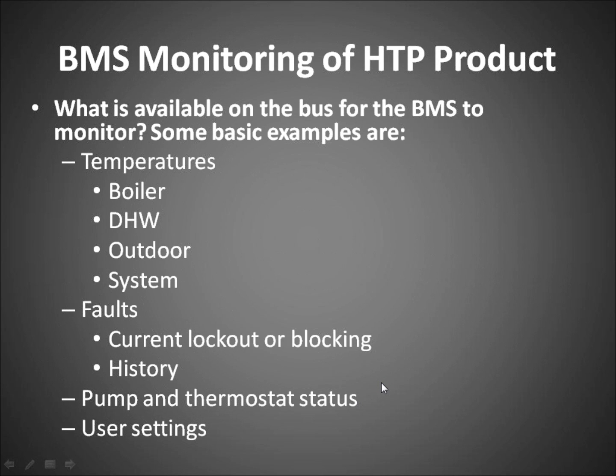BMS monitoring of HTP product. What is available on the bus for the building management system to monitor? Some of the basic examples are temperatures: the boiler temperature, supply and return, DHW temperature, outdoor, system loop temperature. Some of the faults, you can look at your current lockout or blocking codes of what's happening with the connected boilers. Some of the history can also be relayed over the bus. Pump and thermostat status can also be viewed, and user settings can also be monitored.